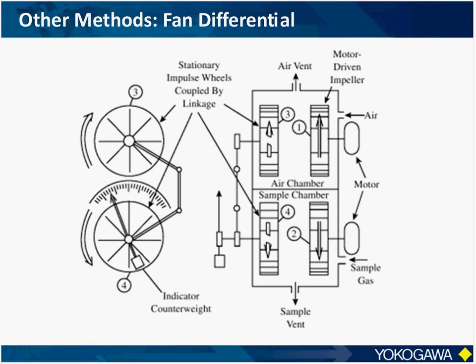And one thing you may notice about this method is that it does have many moving parts that are going to be subject to wear. There are motors, impellers, impulse wheels, and linkages. Now, this will require calibration to compensate for this wear, or a drifting measurement will occur. Now, this method also consumes reference air that needs to be the same pressure and humidity level of the gas being measured. And it also does not take a whole lot of imagination to understand how a dirty sample containing particulates or oil affect the accuracy of this method.